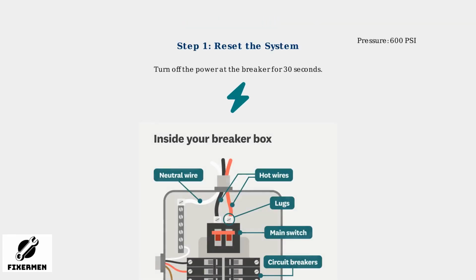Begin troubleshooting by resetting the system. Turn off the power at the breaker for 30 seconds to clear any temporary faults. Next, check and clean the air filter. A dirty filter restricts airflow, which can cause high pressure. Clean or replace it as needed.